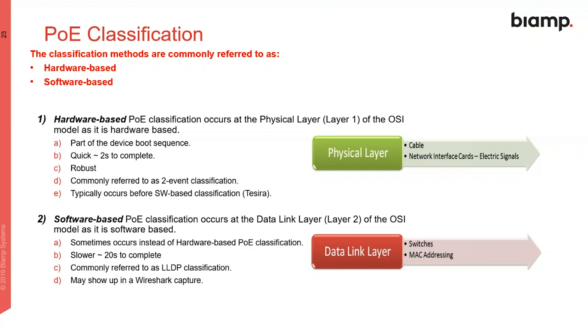The software-based classification method takes quite a bit longer. It can actually take up to 20 seconds sometimes for a device to complete that negotiation process before it fully gets powered up. Some troubleshooting methods are there—you can use Wireshark to do network captures and frequently see that data as well. And I think you'll see more LLDP come up as we get this new standard in place too.